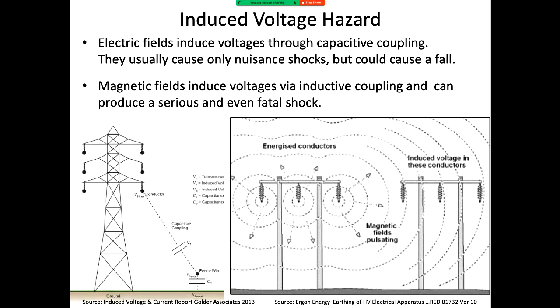The other hazard is step and touch voltages. Again you're not touching the conductor, but say you've got a fallen line. If you step close to it, you'll see these potential lines forming as current goes into the earth. The earth has a certain resistivity.